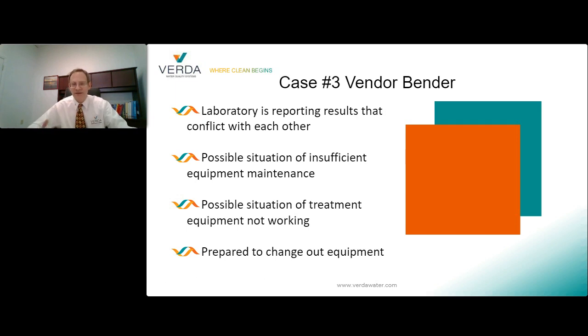Well, why am I saying this? What does this mean? Well, with a conductivity reading of 10 microsiemens per centimeter, that would convert to approximately 6.7 milligrams per liter of TDS. Though to be safe, you could estimate you're probably somewhere between 5 to 8. Notice that the TDS milligram per liter numerical value, 5 to 8, is less than the conductivity numerical value, 10.